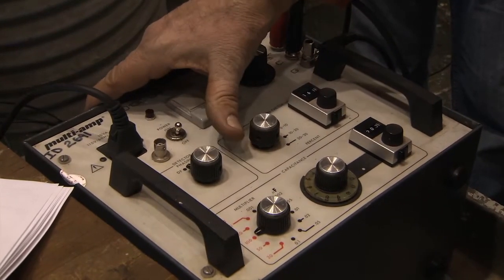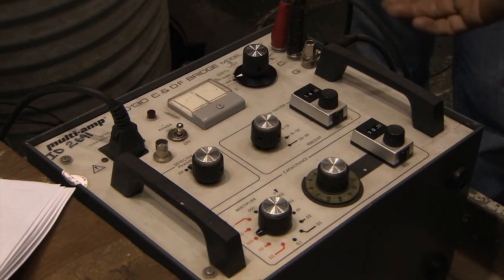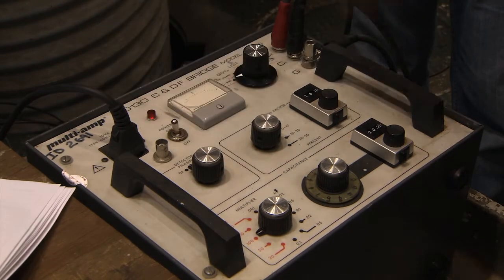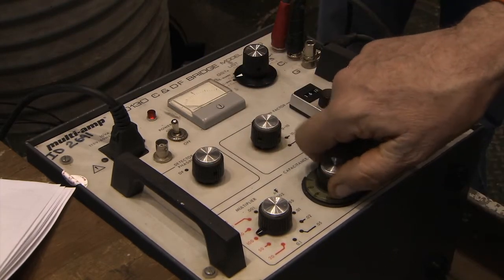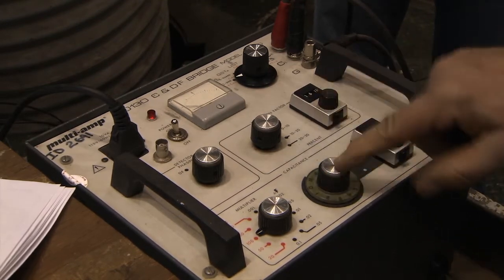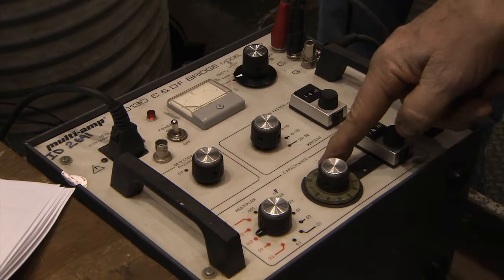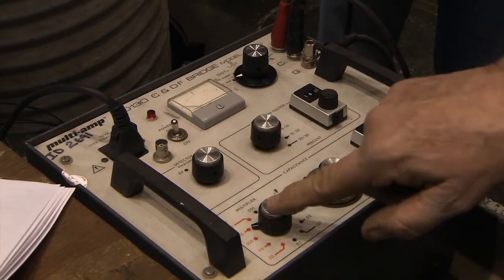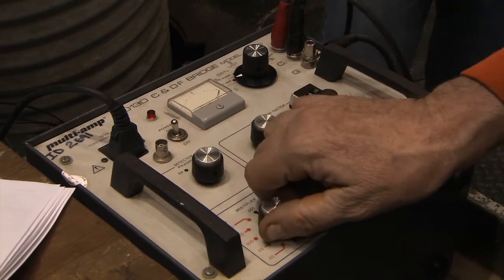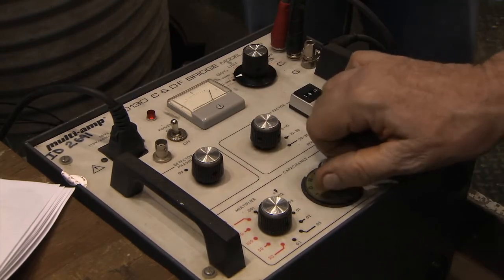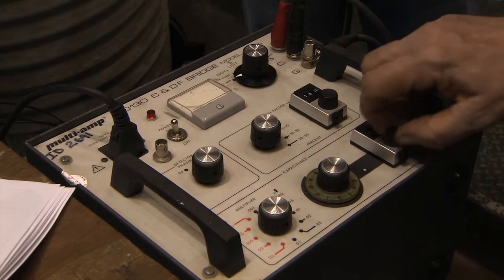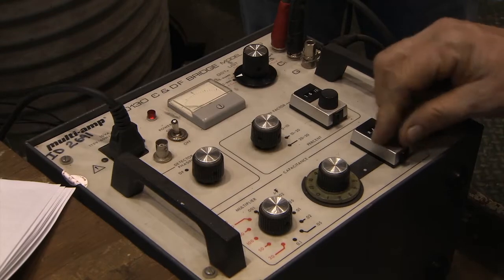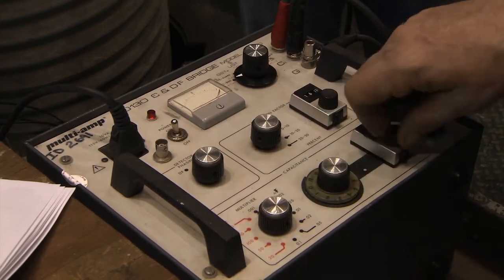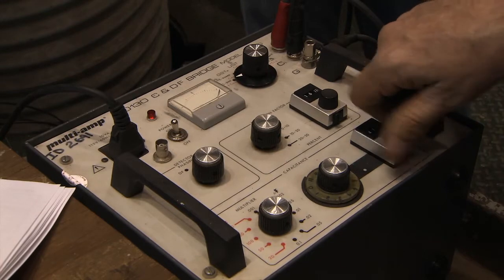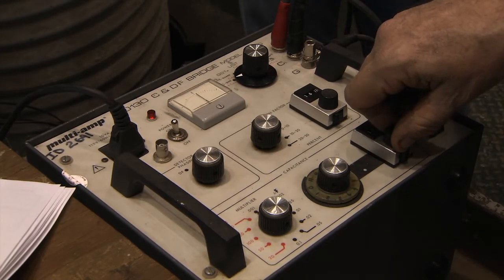So we're going to turn on the power. Get everything with your right hand if you don't mind. Yep. We're going to do the capacitance test first. We're showing low right now, so we're going to try going until we get a reading. Now this gauge here only goes up to 11, so it didn't work there. So now we're going to start going higher with our multiplier to try and get a reading. There we go, we've got our reading. Now we start backing off. Nope, not far enough. Now we've got to go this way. Yep. And there we're at 0.